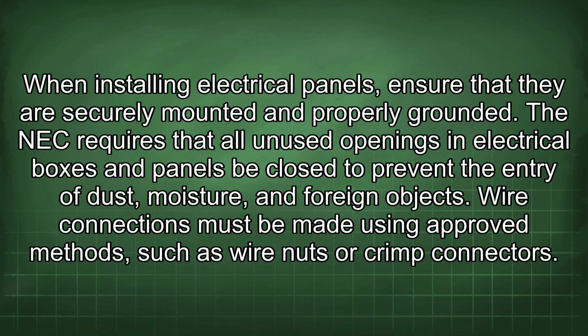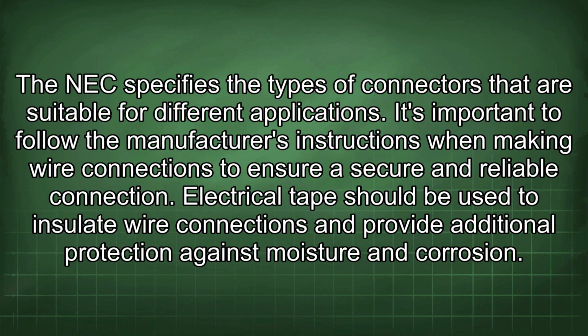When installing electrical panels, ensure that they are securely mounted and properly grounded. The NEC requires that all unused openings in electrical boxes and panels be closed to prevent the entry of dust, moisture, and foreign objects. Wire connections must be made using approved methods such as wire nuts or crimp connectors. The NEC specifies the types of connectors that are suitable for different applications. It's important to follow the manufacturer's instructions when making wire connections to ensure a secure and reliable connection.